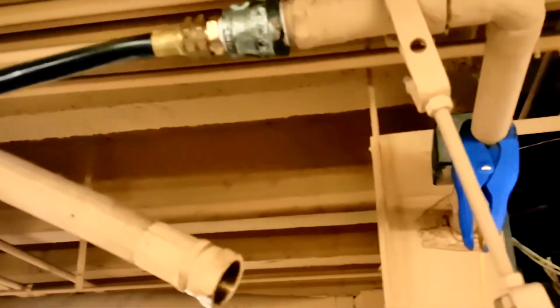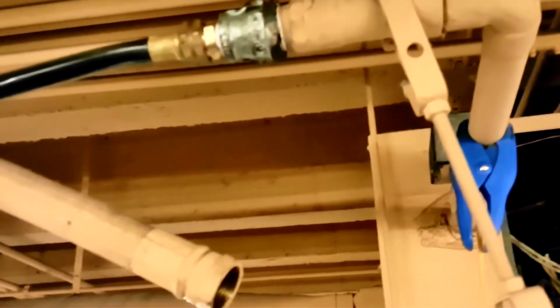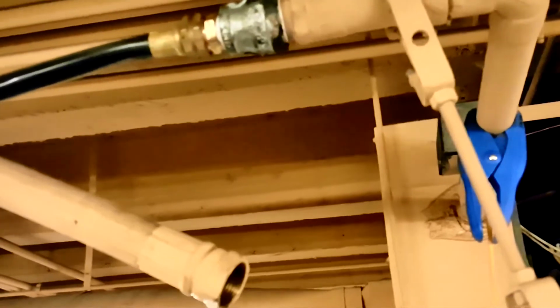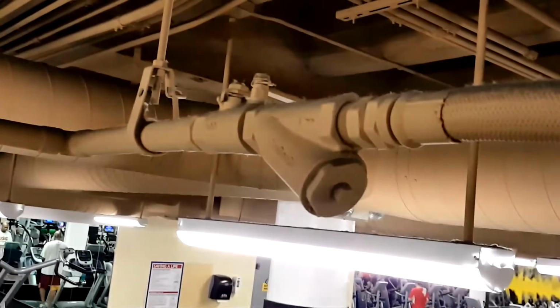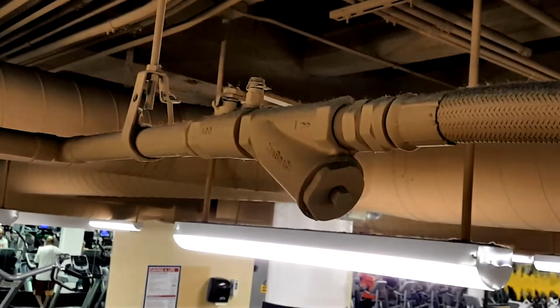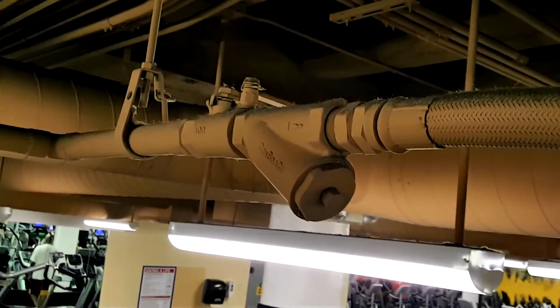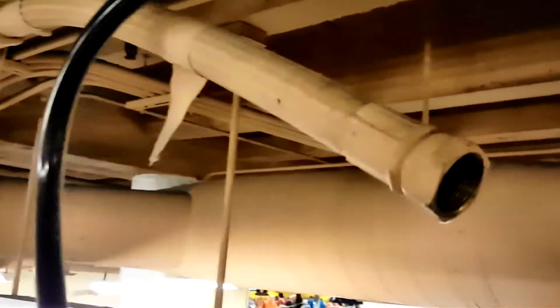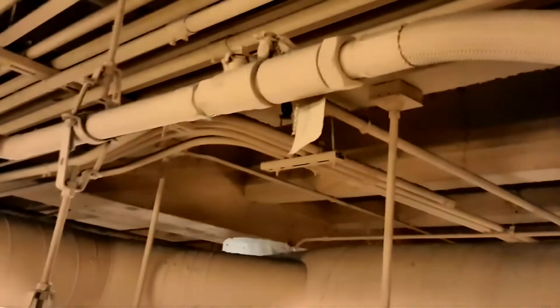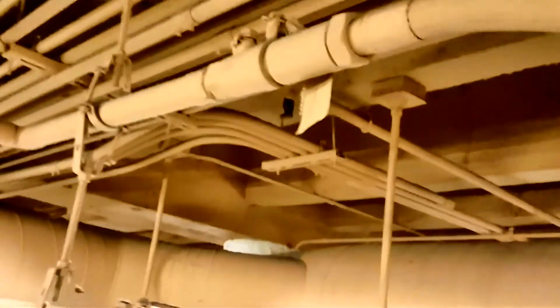Once you're done, you're gonna basically disconnect the lines. You're gonna rinse everything. We're gonna backwash the whole system. The strainer sits right here. We're gonna open up the strainer, clean it out because that one's also plugged. So once we're done with the system, we're gonna be cleaning the strainer, making sure it's nice and clean. We're gonna backwash the system. We're gonna connect the hoses. We're gonna open up the strainer. We're gonna open up the valve on top, pump the water out through the strainer.